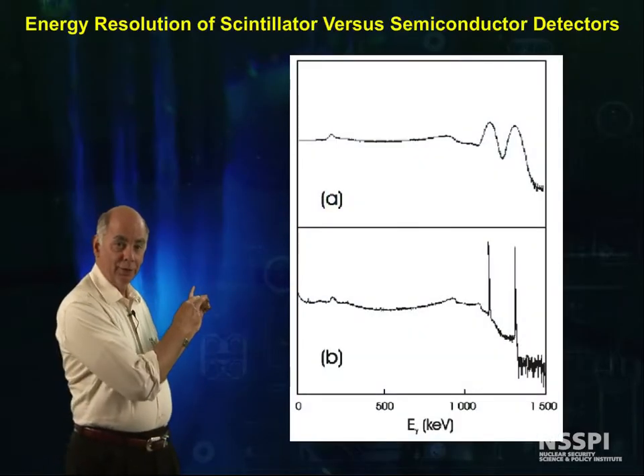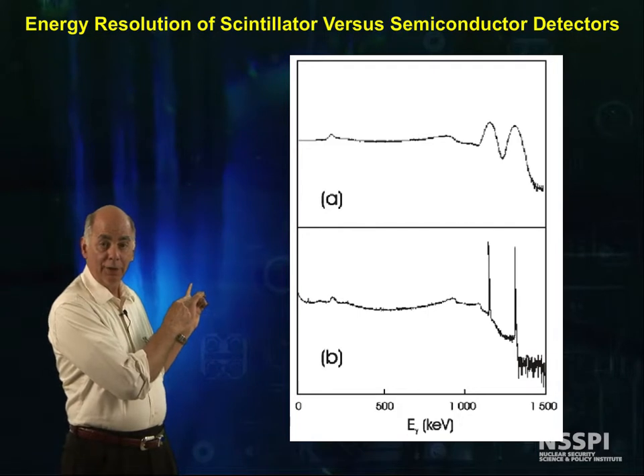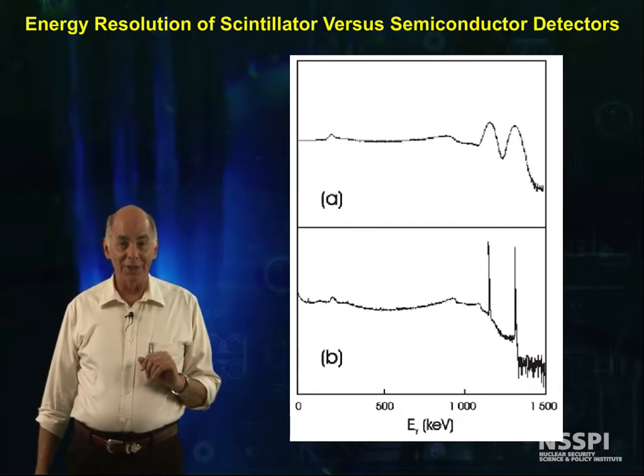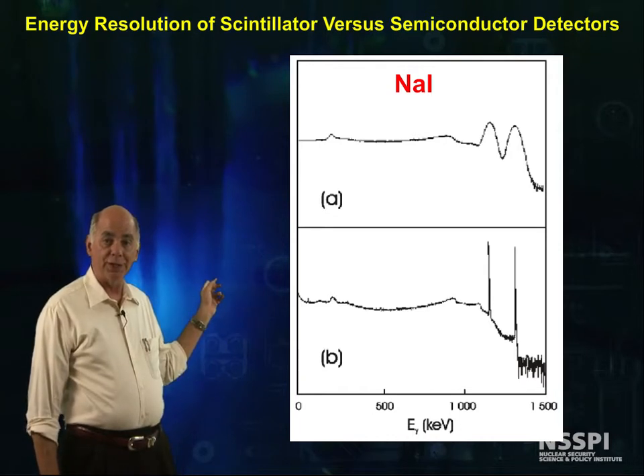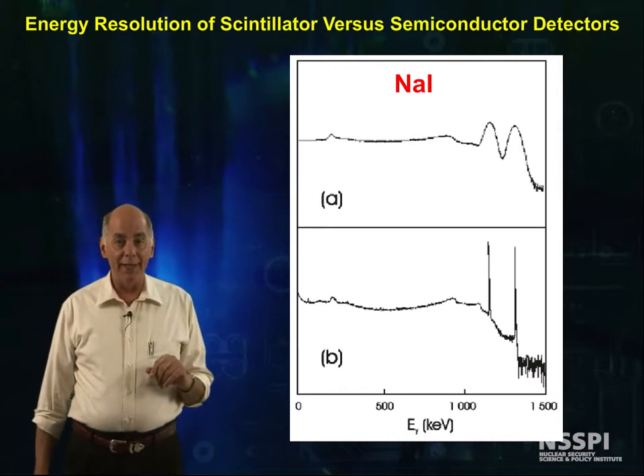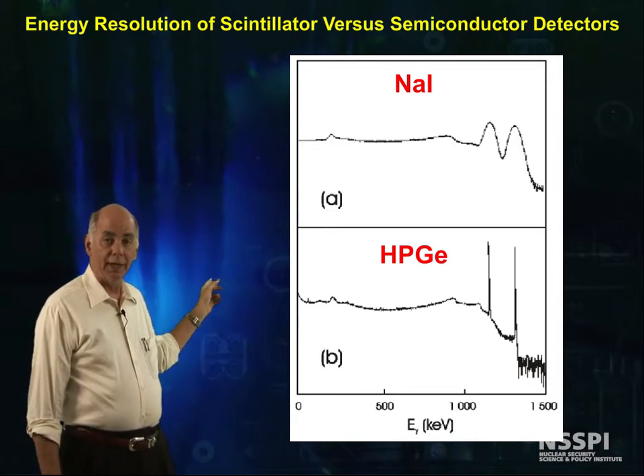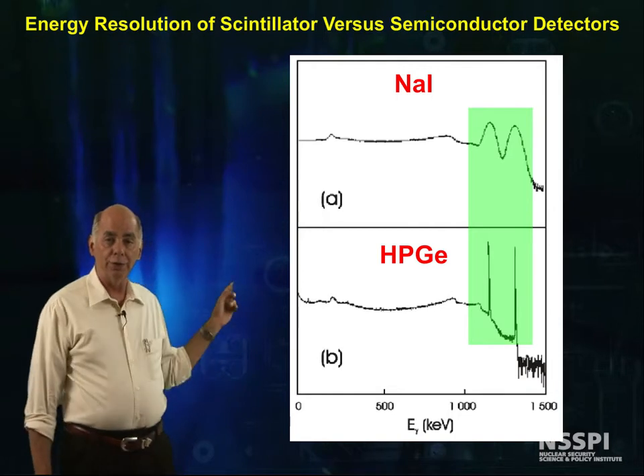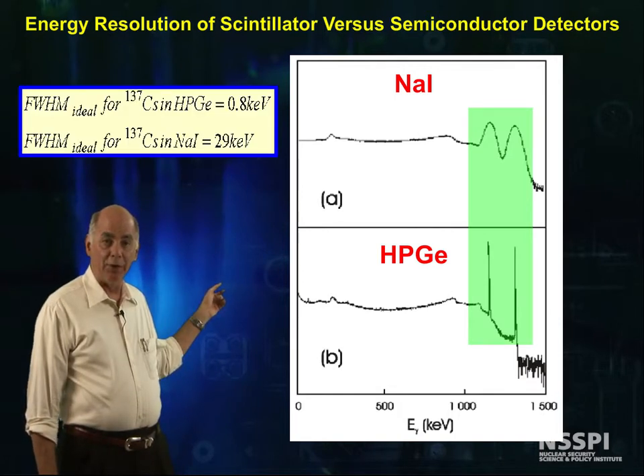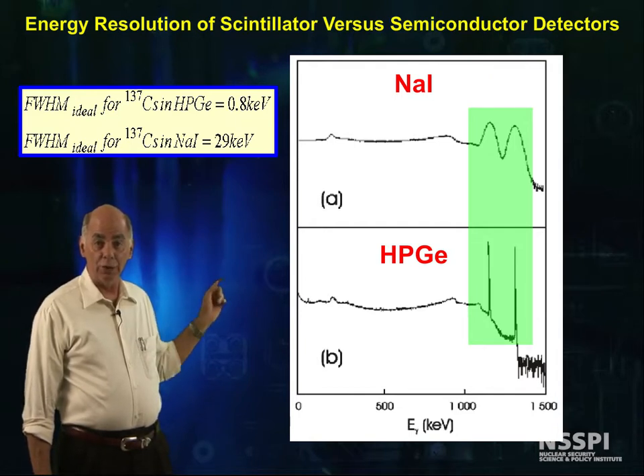You can see here the reason that we go to all this trouble to make and use semiconducting detectors. The first picture is a cobalt-60 spectrum taken with a sodium iodide detector, and the second is a spectrum taken with a high purity germanium. Notice the resolution of the two peaks in the high purity germanium — what a difference 30 times better resolution can make.